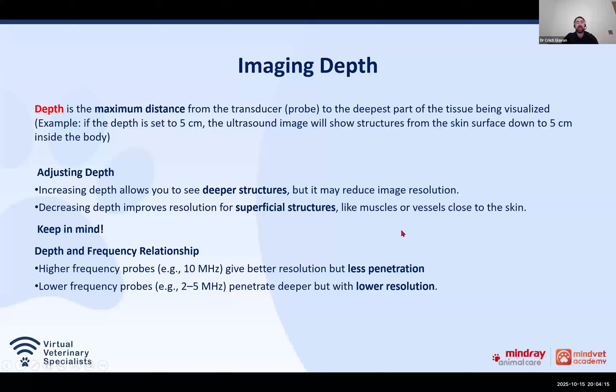Yeah, so depending on the field of interest, the size of the animal and the depth of the structures, having a play with the depth might improve the resolution, and it might give us information that we might miss otherwise. Yeah, and as I was saying here, we do have this relationship between depth and frequency. So always keep this in mind. Bigger depth, we need to lower the frequency, and the other way around, with higher frequency probes, we need to have a smaller depth. Yeah, so it will give us a better resolution and a nicer quality of the image.